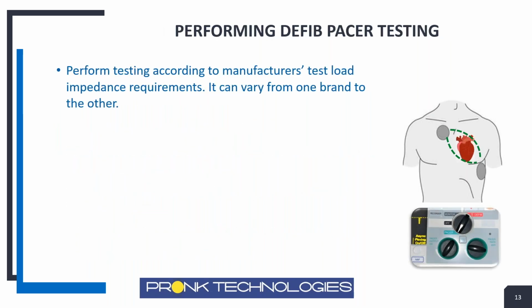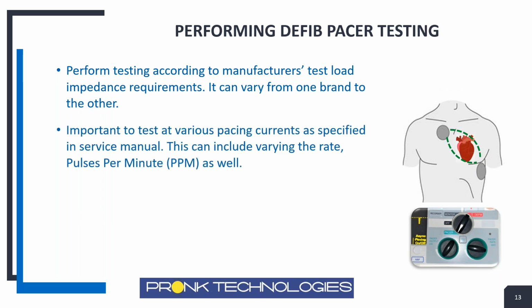So for pacer testing, the same situation applies, and it's easy to get tripped up: the manufacturer also specifies the impedance you're supposed to test pacing on. It could be different, and not all manufacturers want you to test at the same exact impedance. So you have to make sure you've programmed your analyzer for the right impedance based on what that brand requires. The manufacturer also wants you to test at various pulses per minute. They don't want you to just test one test point. You want to make sure that at various ranges of current and pulses per minute, the pacer function works as it should.